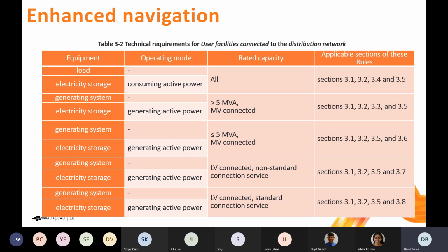One of the questions we often get is, well, what if my facility includes a combination of devices? So you might have a load facility that's also going to have some generation connected as part of that same facility. And so the answer there is, well, you take the load component, and the load component needs to meet the requirements for loads, and the generation component needs to meet the requirements for generation. And so you can look then through these tables and work out which requirements apply to your facility.